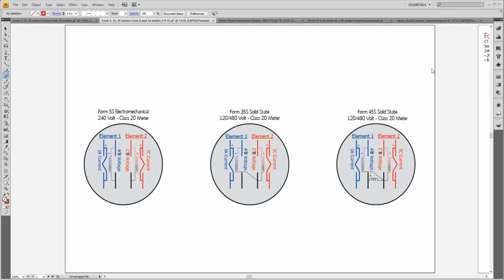Okay. So the difference between the electromechanical 5S, a 35S, and then the 45S. With this one, when I was talking about it, this is set up for how we wire for three-phase, 3-wire delta. Each one of these would be a connection for the three-phase 3-wire delta.